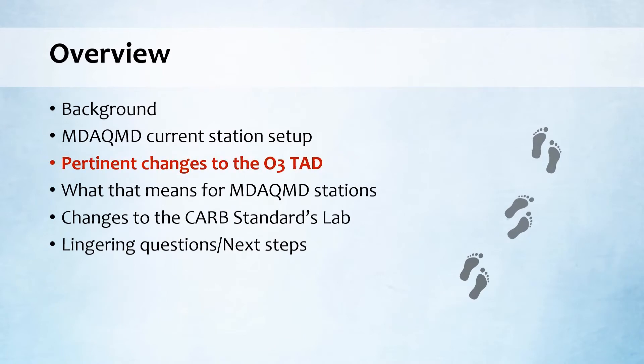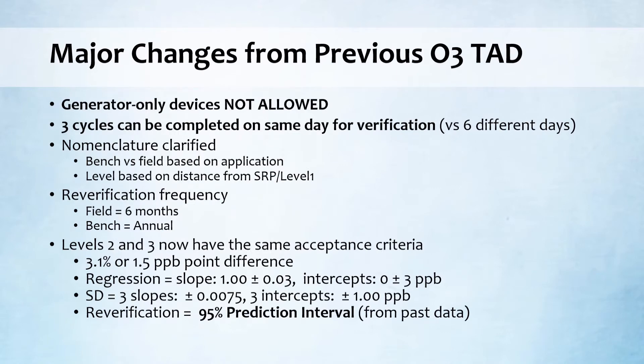Next I'll discuss pertinent changes to the Ozone TAD. Here in a nutshell is a list of the major changes for the 2020 Ozone TAD compared to the previous 2013 version. The biggest one for our district is that generator-only devices will no longer be allowed for use as a transfer standard. On the upside, for the initial verification, three cycles can be completed all in the same day, whereas previously six different cycles were required on six different days. So that should make things easier.